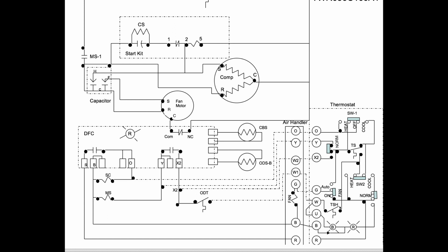So let's go through this thing. When this heating thermostat down here closes, now that's second stage heat. That means the heat pump is operating through Y up here, but it can't keep up with the load, and the temperature continues to drop. So when it continues to drop about 2 degrees, this thermostat here is going to close, pass power through W to W1, and that is going to energize, we'll say this electric furnace, and it'll energize maybe two elements.